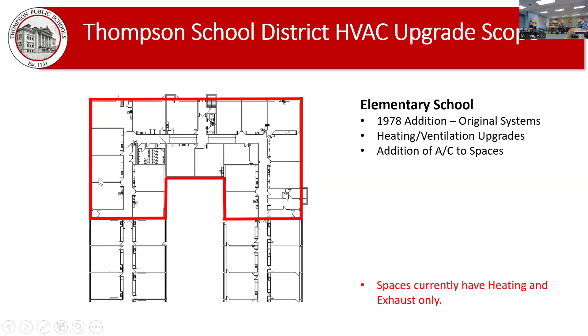For the elementary school, at that door there's an access door. That portion in back is similar to the high school second floor, where it's a perimeter heating zone with radiant heat. There's one exhaust louver in each area where we provide exhaust air, and makeup air comes through infiltration or through the corridor under the door. No supply air, no return air, no real units.